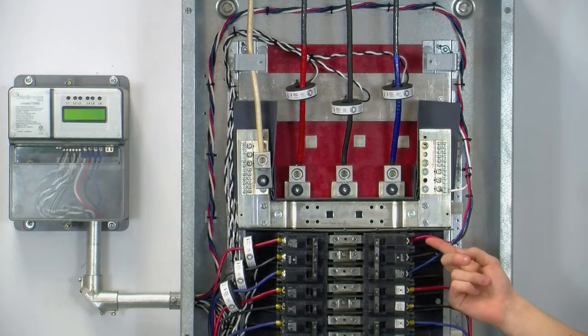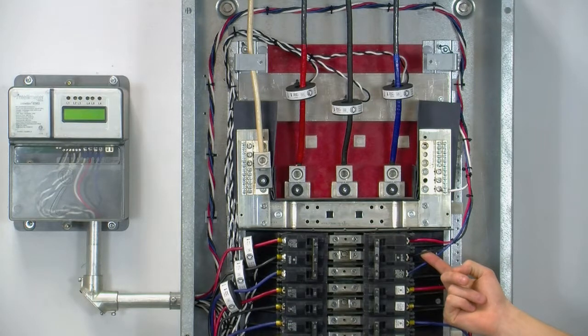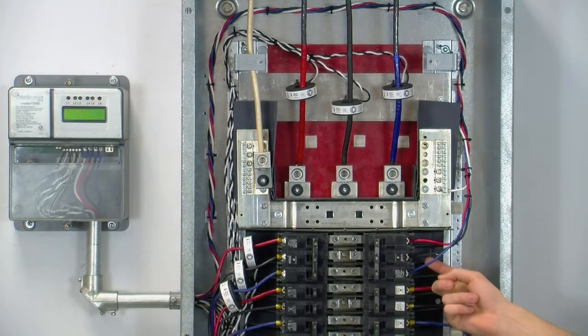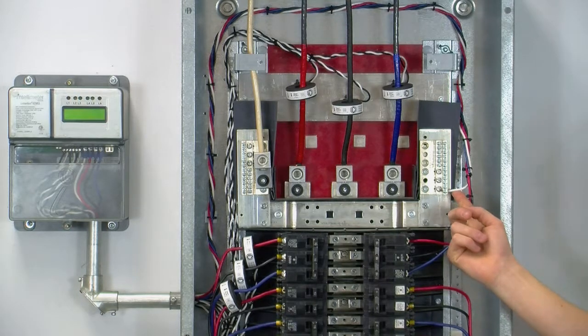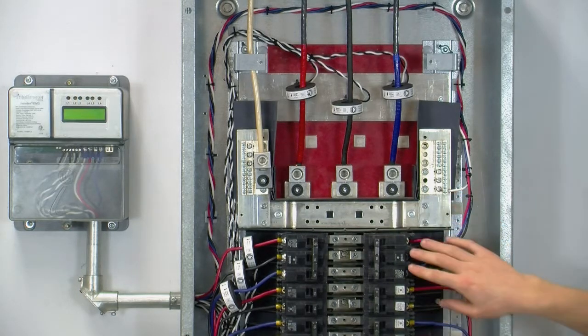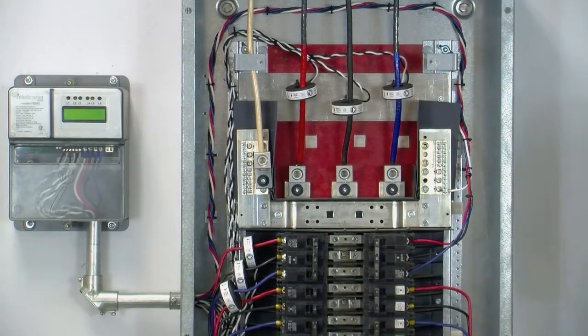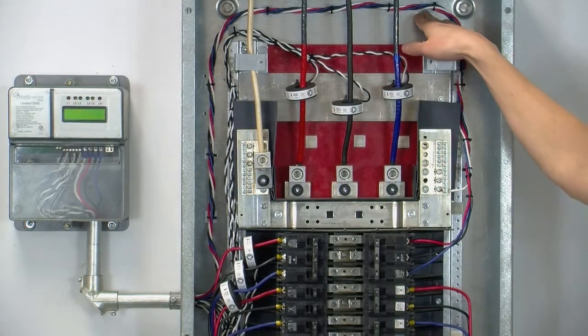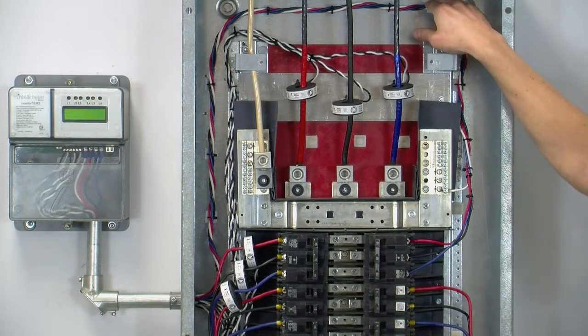In Canada, we use red for phase A or line 1, black for phase B or line 2, and blue for phase C or line 3. And lastly, we use white for neutral. So we're going to terminate one end of the wires into the breaker and neutral block and run the four wires back to the meter. You can use adhesive mounting bases in combination with zip ties to cleanly dress your wires back to the meter enclosure.